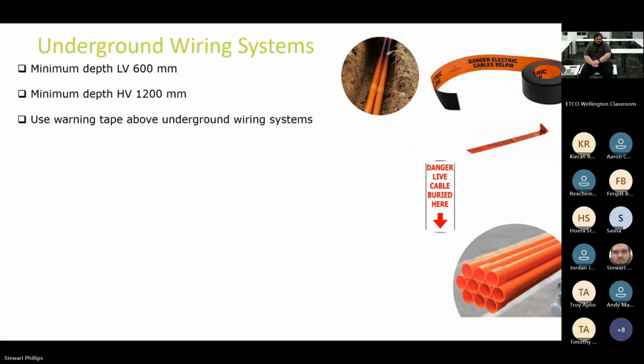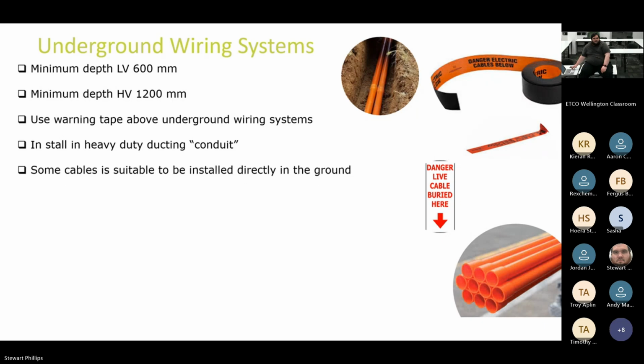So 600, buried conduit or cable, cover with sand, another 100 mil, danger tape, fill the rest of the trench. Install in heavy duty ducting conduit. So it is called ducting, but it is a form of conduit. Cool. Some cables are suitable to be installed directly in the ground, but we need to make sure that these cables are designed for this purpose.